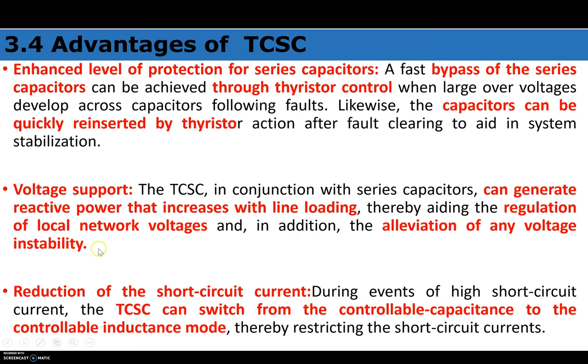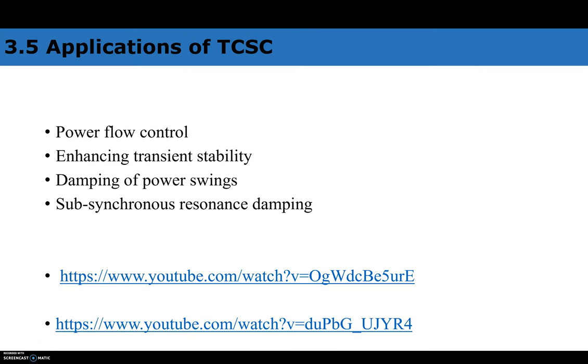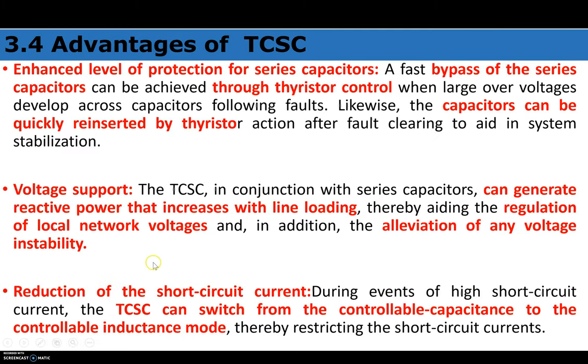TCSC also gives reduction of short circuit current during events of high voltage short circuit. TCSC can switch from the controllable capacitance mode to the controllable inductance mode, thereby restricting the short circuit current. When a short circuit occurs, switching the thyristor controlled reactor on introduces additional reactance into the circuit, which reduces the short circuit current. Reactance plays a very important role in controlling short circuit current. These are the advantages of TCSC.